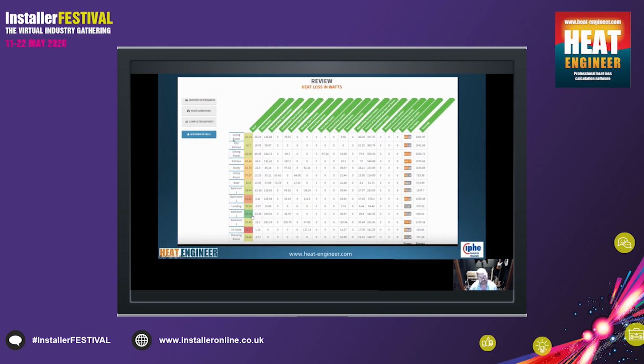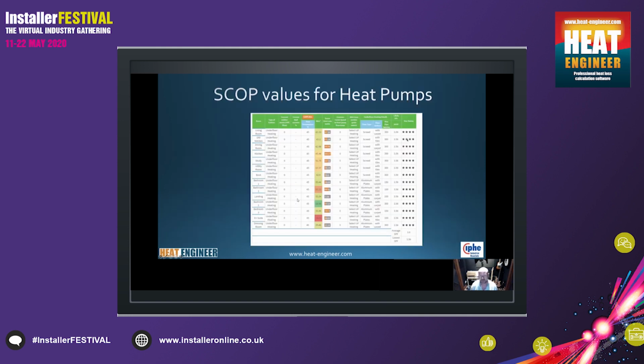We're seeing that some of these, like that living room, for argument's sake, it just needs 42 watts per square meter, as you can see. And again, it gives you the total watts of what that room requires, which is 567 watts, or half a kilowatt. It also gives you all of your coefficient values for heat pumps, etc., and it starts to give you a star rating of what is going on with your average seasonal performance figures at the bottom here.